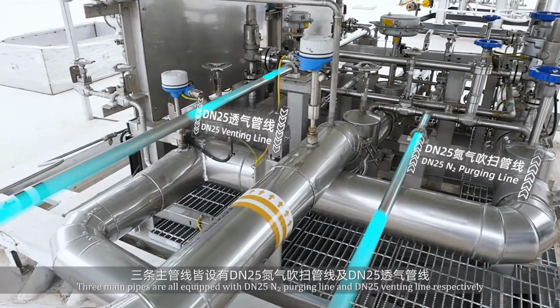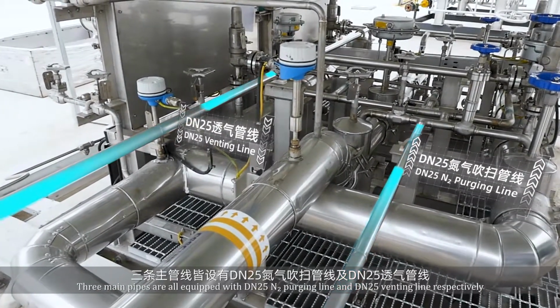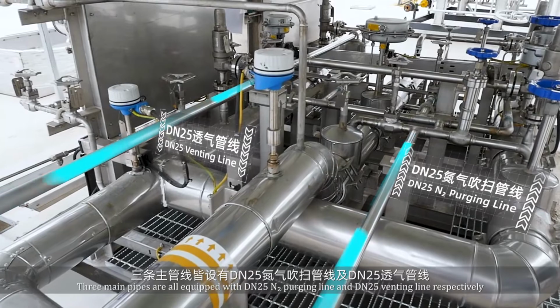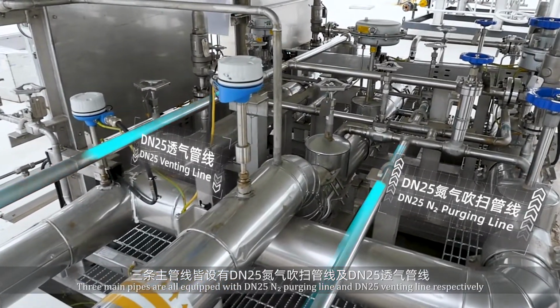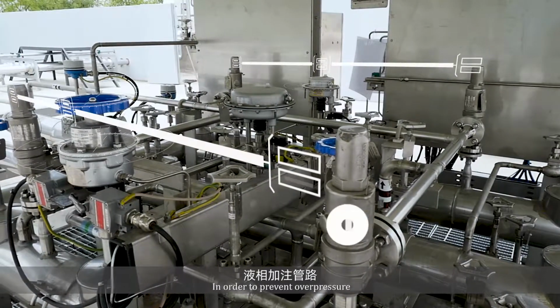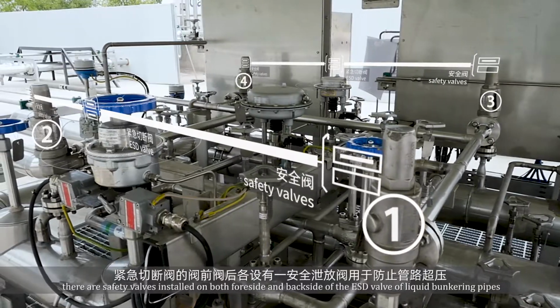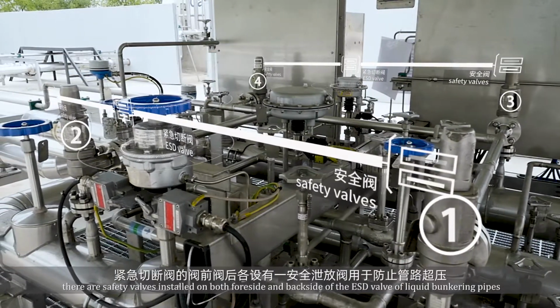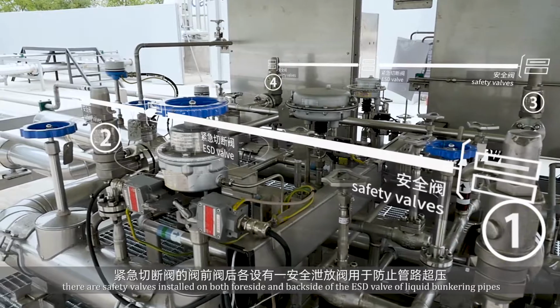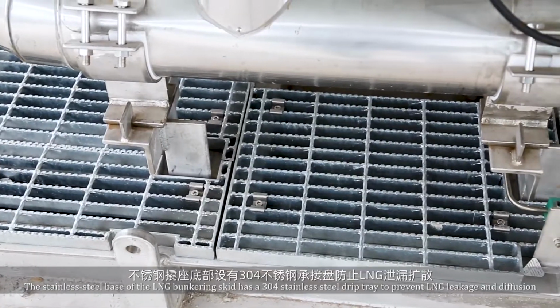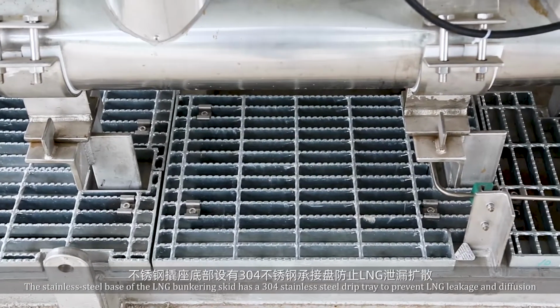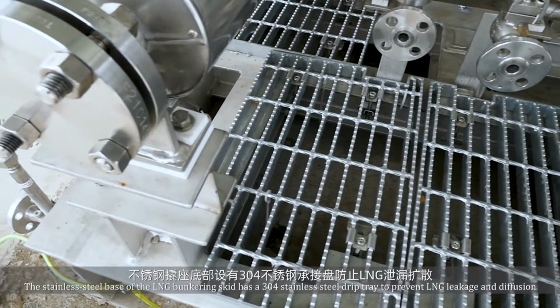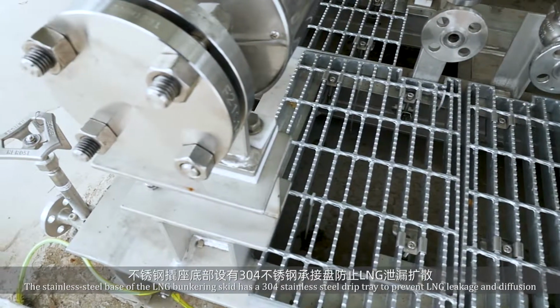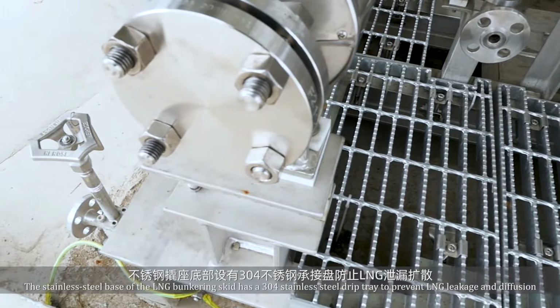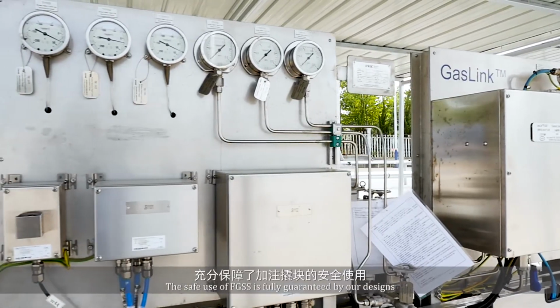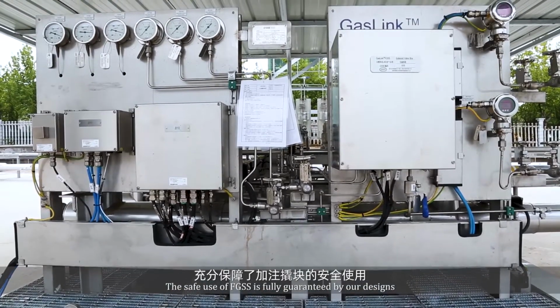The 3 main pipes are all equipped with a DN25 nitrogen purging line and a DN25 venting line respectively. In order to prevent overpressure, there are safety valves installed on both the foreside and backside of the ESD valve of the liquid bunkering pipes. The stainless steel base of the LNG bunkering skid has a 304 stainless steel drip tray to prevent LNG leakage and diffusion. The safe use of FGSS is fully guaranteed by our designs.